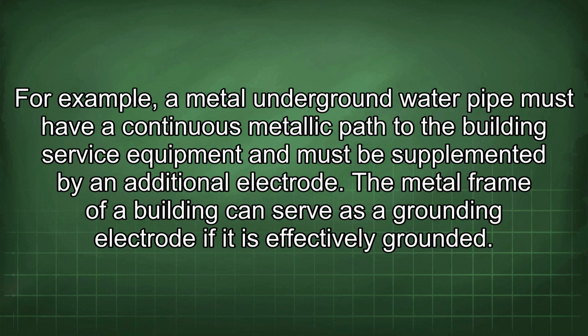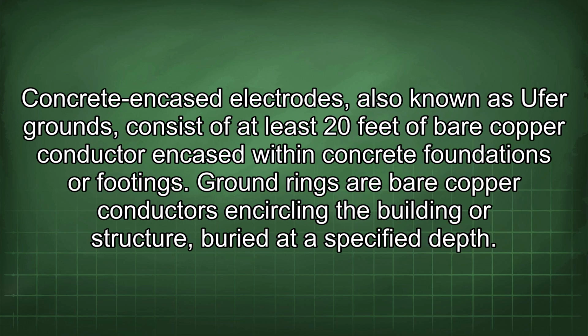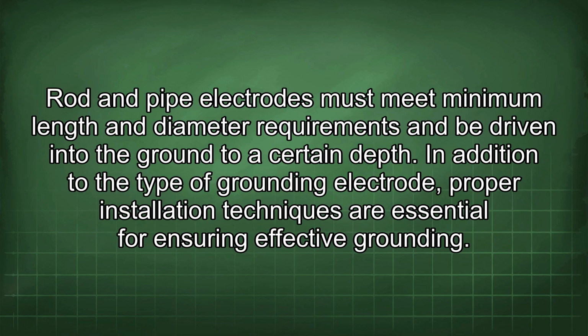The metal frame of a building can serve as a grounding electrode if it is effectively grounded. Concrete encased electrodes, also known as Ufer grounds, consist of at least 20 feet of bare copper conductor encased within concrete foundations or footings. Ground rings are bare copper conductors encircling the building or structure, buried at a specified depth. Rod and pipe electrodes must meet minimum length and diameter requirements and be driven into the ground to a certain depth. In addition to the type of grounding electrode, proper installation techniques are essential for ensuring effective grounding.